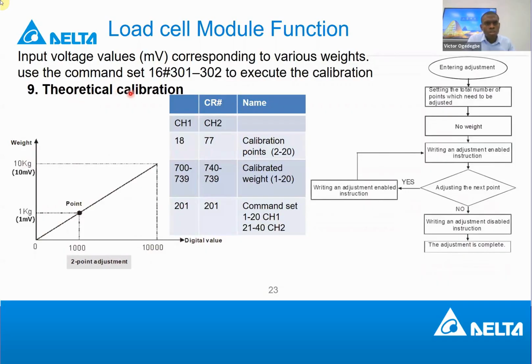And for this theoretical calibration, you don't need to put weight on it. What you are doing is that in the place where you normally would have written the weight, you just write the voltage, the millivolt. 1.0 means 1 millivolt, 2.0 means 2 millivolts. So you write 2 millivolts, when 2 millivolts is equivalent to the digital value that you have set. You are just using millivolts, not real weight like the first case. It's theoretical, it's not practical.